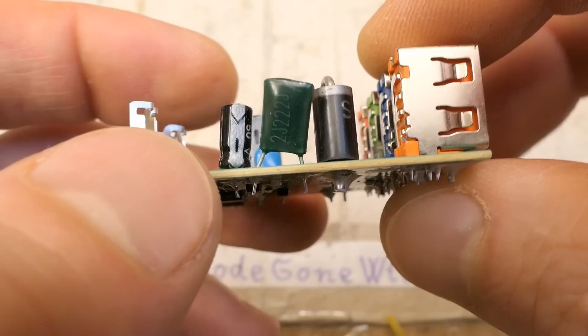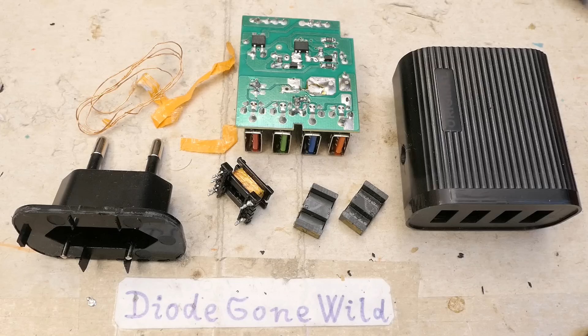The proper capacitor for this application is a class Y1 capacitor, which I believe is tested at 8 kilovolts. Very often they use a 1 kilovolt capacitor only, which is already quite horrible, but in this case they went even further and used a 630 volt only capacitor here. This is probably the lowest voltage rated capacitor between the primary and secondary side of a switching power supply I've ever seen. So let's sum it up.